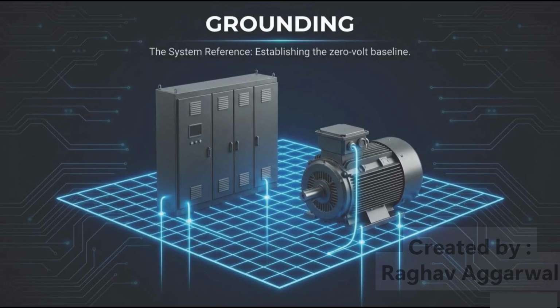While earthing focuses on handling fault conditions, grounding supports normal everyday operation. Together, these concepts complement each other. One protects during abnormal events, while the other supports stable performance during normal operation. How is grounding related to human safety? Grounding plays an important role during fault conditions. Let us see the comparison of two situations.